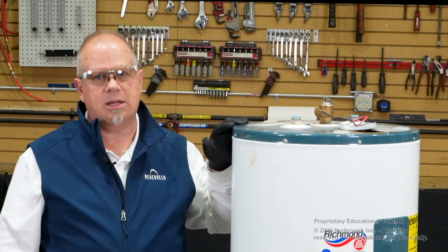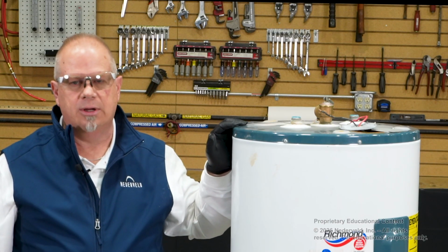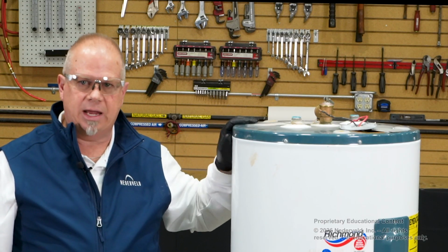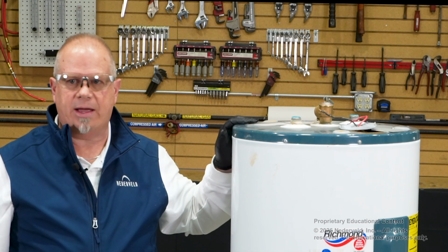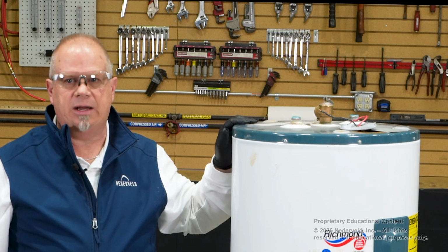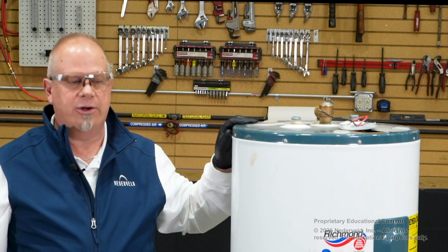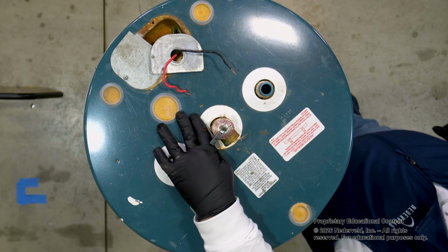Lack of maintenance is a common defense of manufacturers. For example, most tank style water heaters have a manufacturer requirement that they be drained and flushed annually and the anode, which is usually underneath a plug, inspected. Water softeners that inappropriately add salt to the water system can accelerate corrosion, especially true of tankless water heaters.